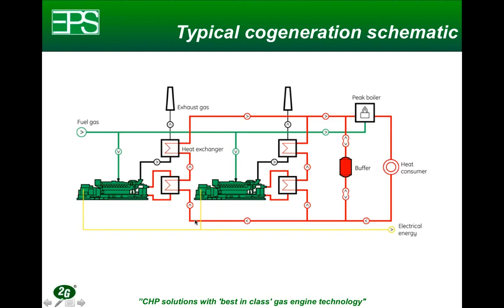So in this case, we're showing a diagram that produces hot water as a byproduct from producing power. So hot water here picks up the heat from the engine jacket water, oil cooler, and aftercooler. It then will flow to another heat exchanger that will pick up the heat from the exhaust, and then the water, which typically is at about 90 degrees Celsius, 190 to 200 degrees Fahrenheit, will then flow to the customer.